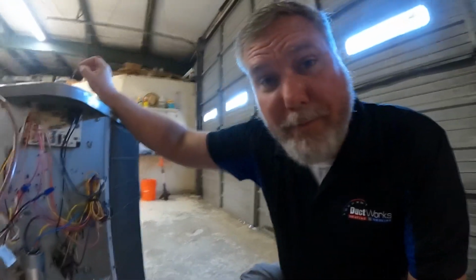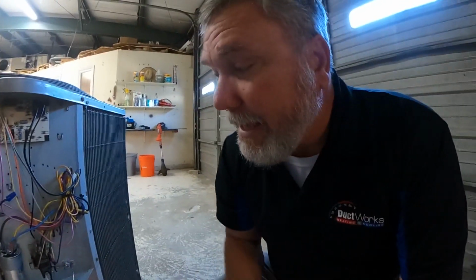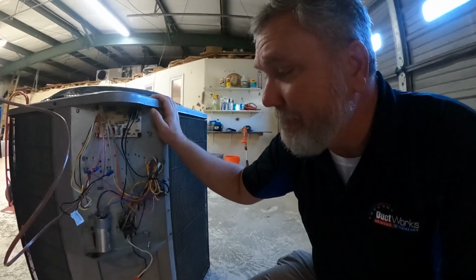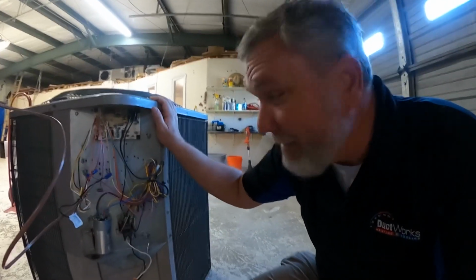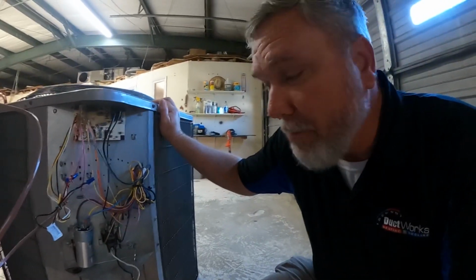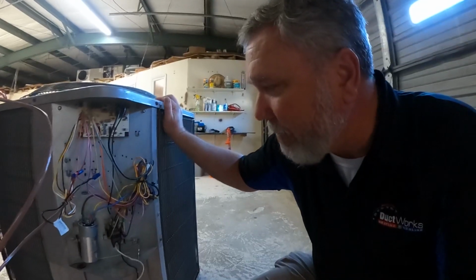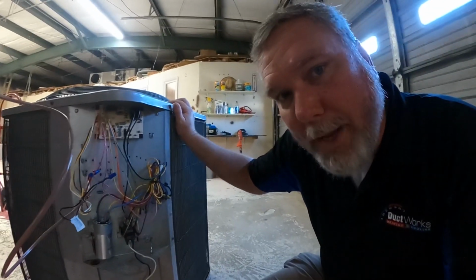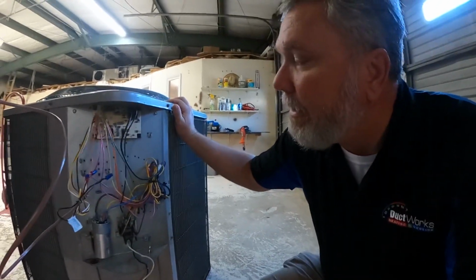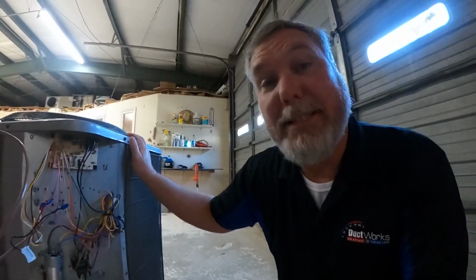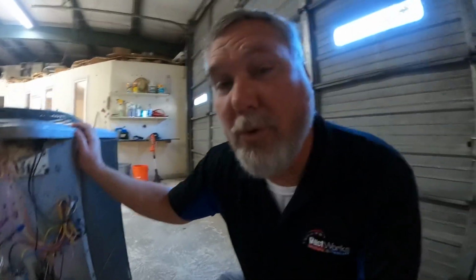We also check the contactor. A contactor is like a switch. That's what says click, turn on compressor, click, turn on fan. So that's very important too. And after years of off and on, off and on, off and on, they can get worn down. So we go through and check those out. We also check defrost control boards. That's what this is. Now, when it gets good and cold outside, these systems start to frost up. They get a little bit of ice on them. You might have looked outside and seen little bands of ice on the outdoor unit. It's normal to have some. But once the temperature gets to a certain point, there's a sensor that says, hey, it's time to go into defrost mode. So it switches over to defrost mode and thaws everything out. So it's normal to see a little bit of frost on the outdoor unit, especially when it's really, really cold outside.